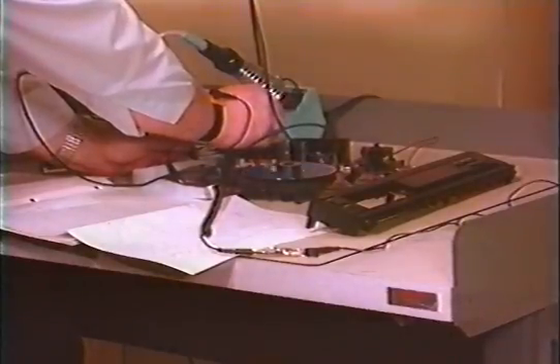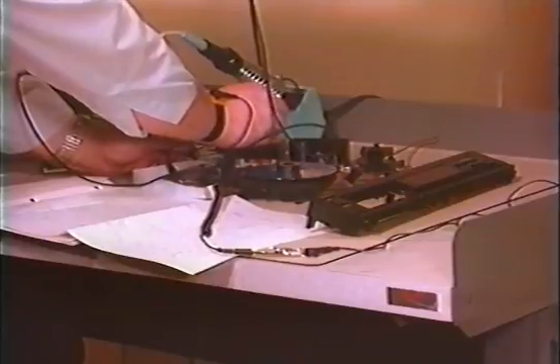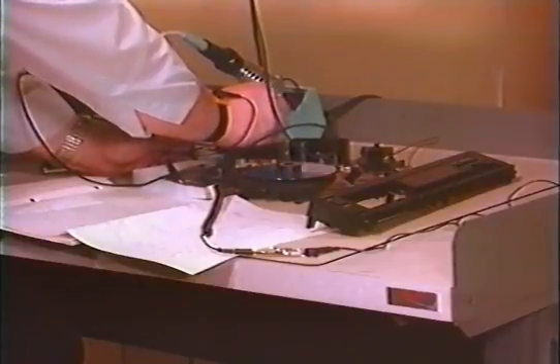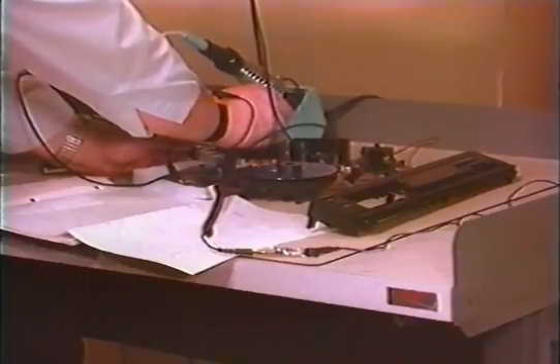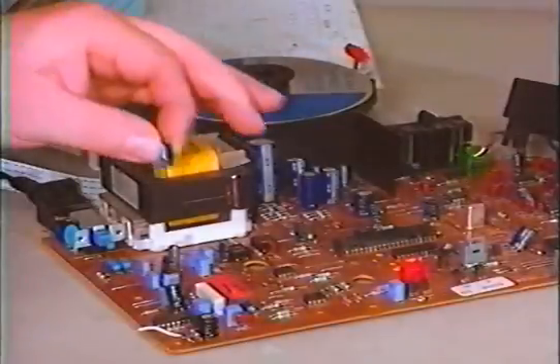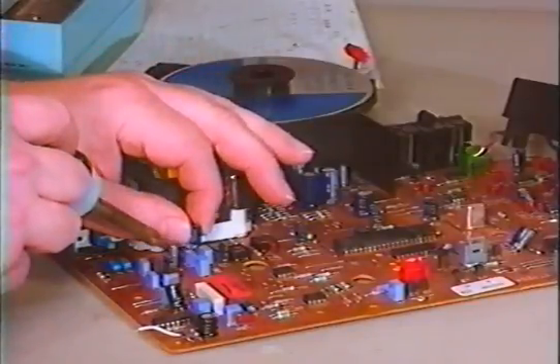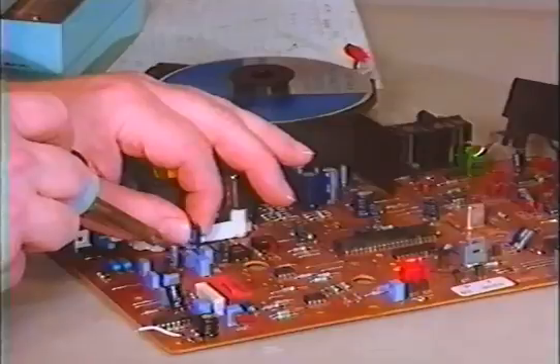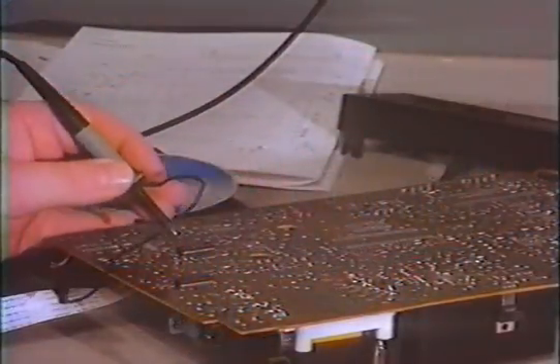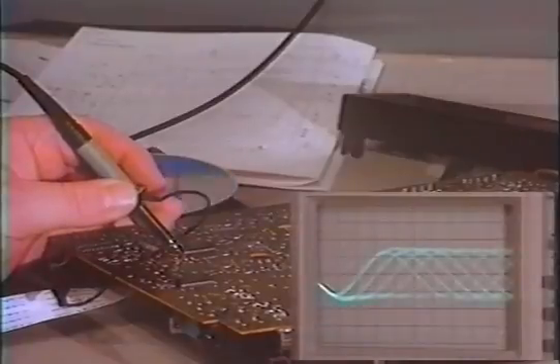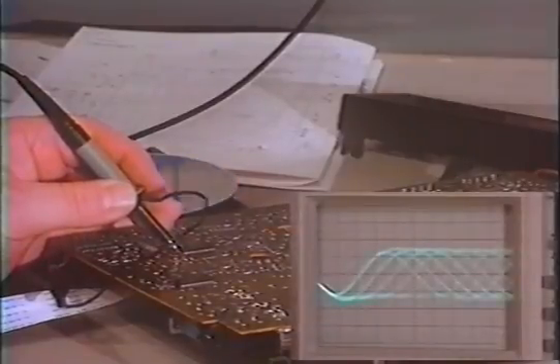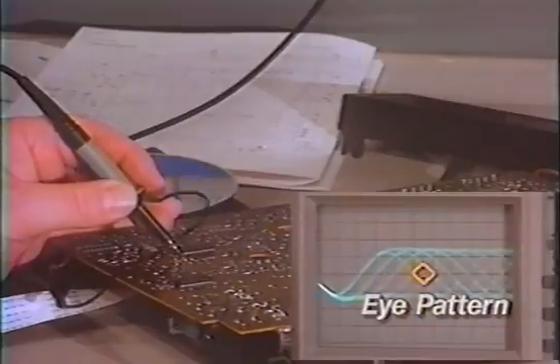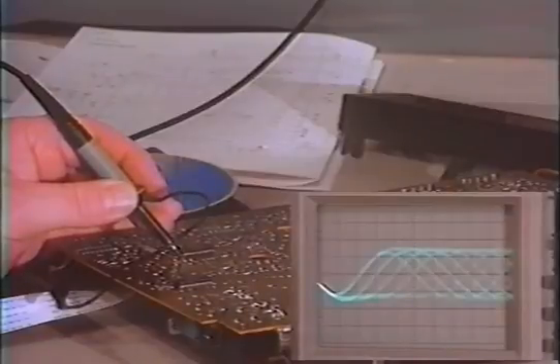Adjustment procedures vary from one system to another. Some units are digitally adjusted via a computer, and some units are self-adjusting. The service manual of the unit being serviced should be consulted before attempting any adjustments. In most cases, adjustments are necessary only after the replacement of a component. In some cases, the test point for the adjustment procedure may only need to be checked for verification of the correct waveform or signal level. In many cases, these test points can be used when troubleshooting the unit to verify proper performance.